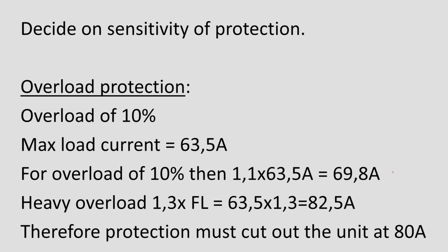Now, just a note, if your cable is only able to carry 70 amps, but your protection is only set for 80 amps, now we have a mismatch in terms of the cable carrying current capacity and the protection that will operate. Now, if the protection is only going to operate after 80 amps, then your cable will have to be able to handle above 80 amps. So this is where we need to coordinate the cable size to the protection. That is why it's always best practice to over-specify on the cable size, because we don't want to have a fire because of the cable burning.